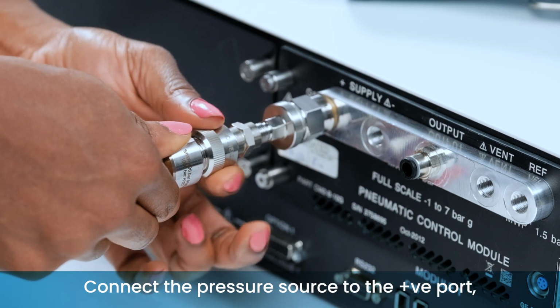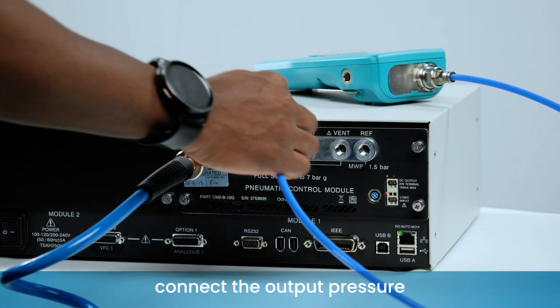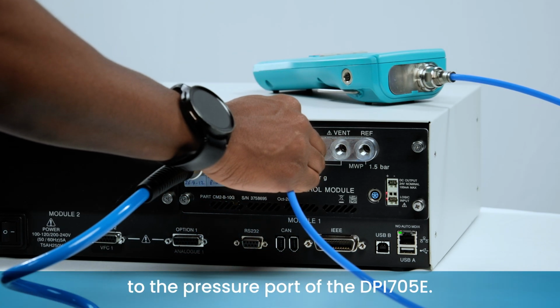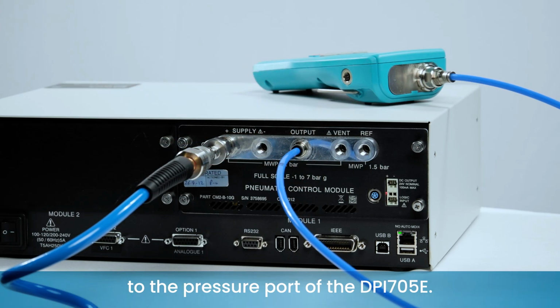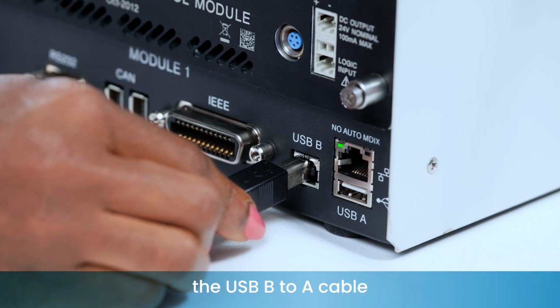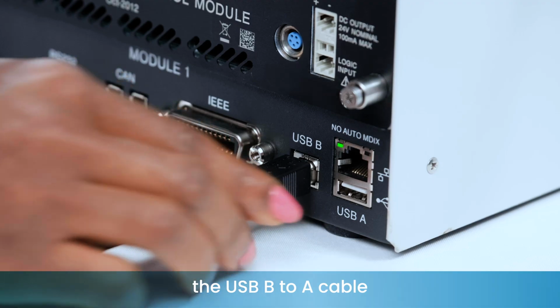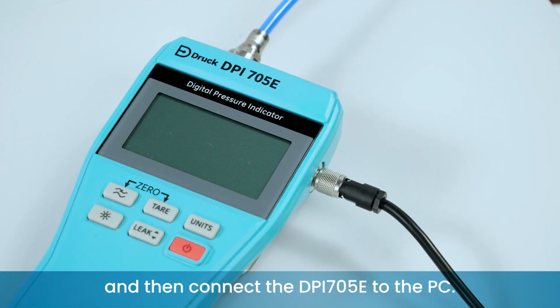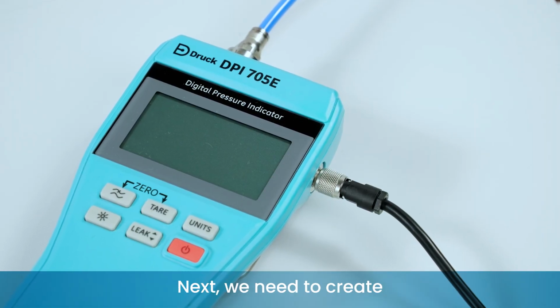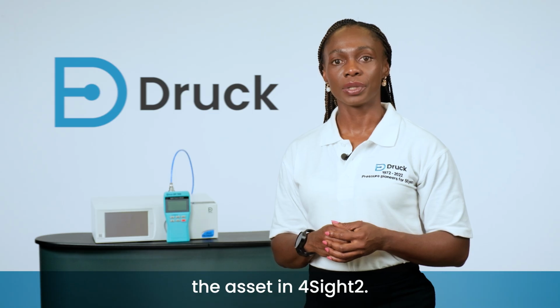Connect the pressure source to the positive port, connect the output pressure from the PACE to the pressure port of the DPI705E. Connect the PACE to the PC using the USB B to A cable, and then connect the DPI705E to the PC. Next, we need to create the asset in 4Sight2.